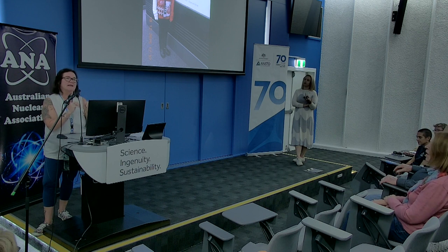So if a breaker trips, we can see in the control room what tripped it without sending a field operator to go and verify it, especially if it needs to be done in a timely manner. We can also remotely monitor temperature changes over time and power. There are basic gauges at the Bruce and Darlington stations that aren't really exact, but our engineers now, through this remote monitoring, can pull up, say, the main output transformer and see that every morning when we put a bit more load out, it's blipping above where it should be and then coming back down. The operators in the control room aren't going to see that trend, but for long-term trending, it's already happening, and there are a couple of really great companies out there focused on AI and those changes, more so in monitoring than in control right now.